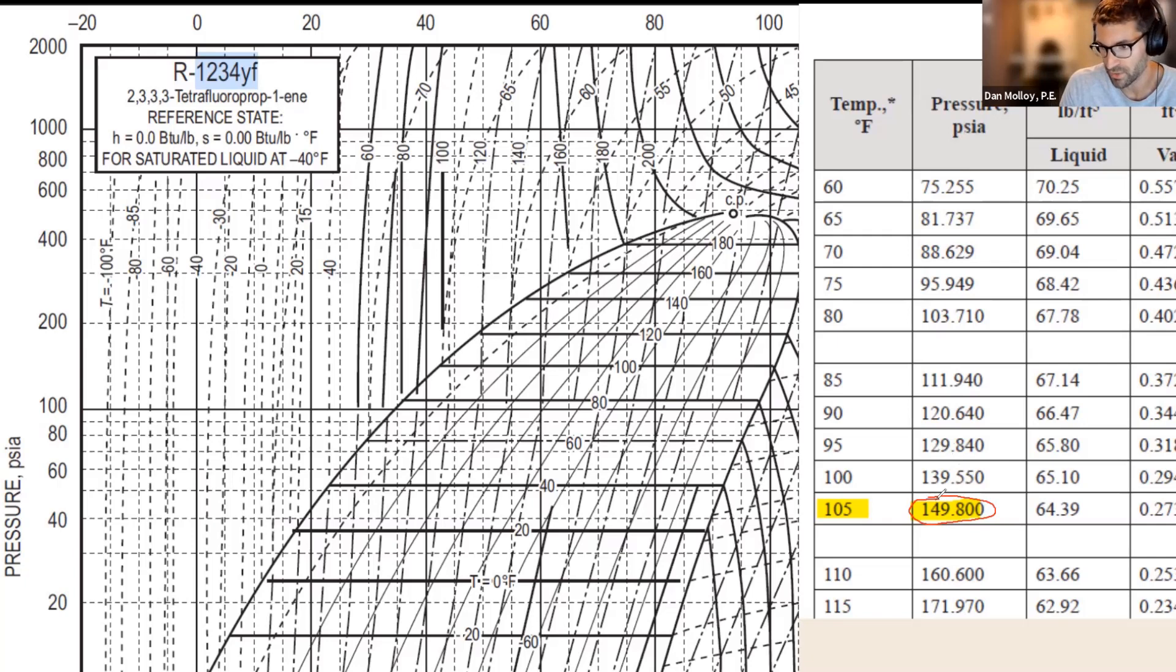That we'd never be able to see the difference anyway. So we'll say that's the operating pressure of the high pressure part of the process. The associated temperature at that pressure is 105 degrees. And that's handy to know because now we can have a look at these temperature lines and we happen to have 100 and 120 right there. And now it's a little easier to visualize because we could sort of say, okay, where would 105 be in between these two?